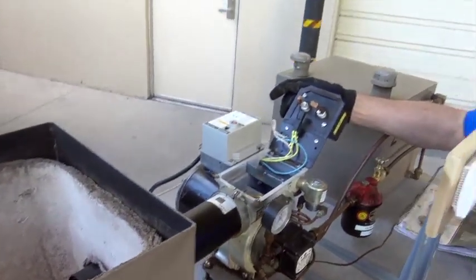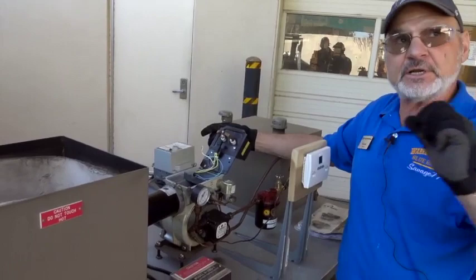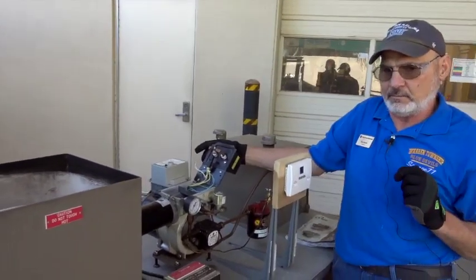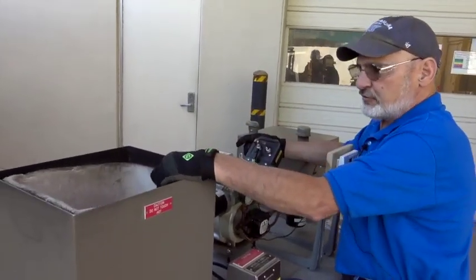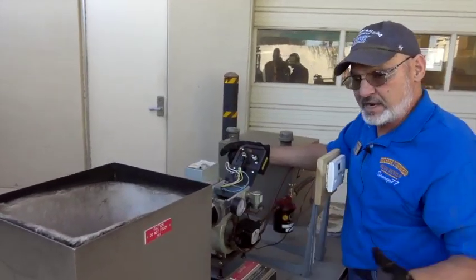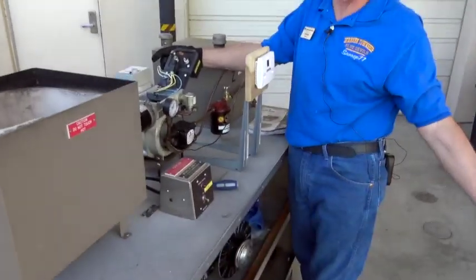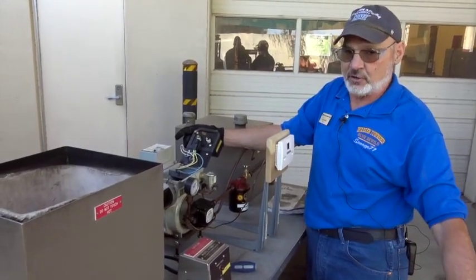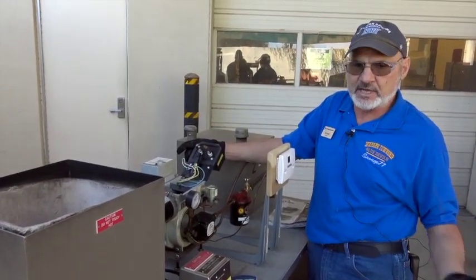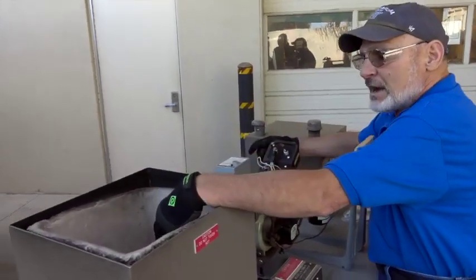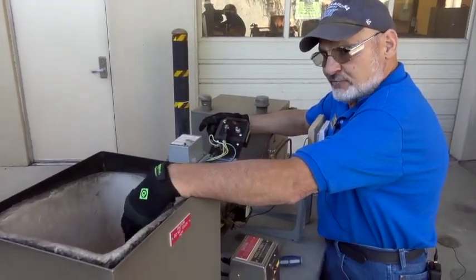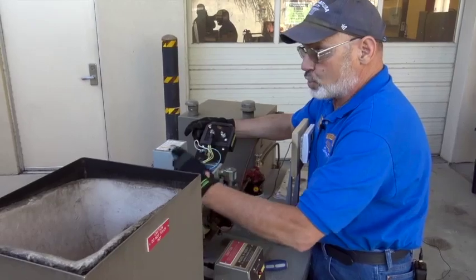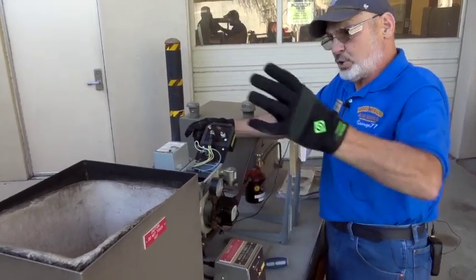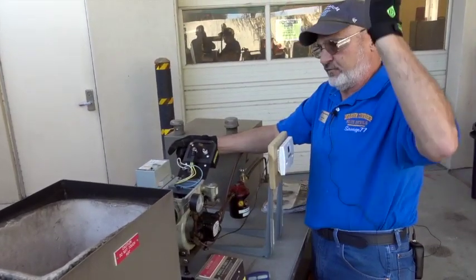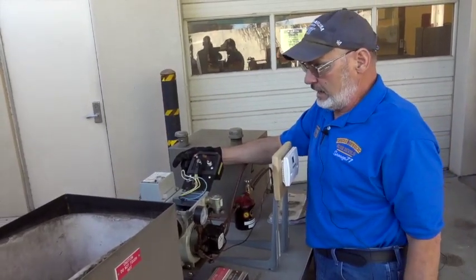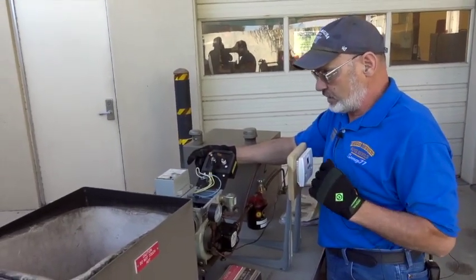Unlike natural gas or propane gas, it's not going to dissipate into the atmosphere. The residual fuel will sit there for a long time. You've been at a gas station where people dump fuel in the gas station. It sits there for a long time. In fact, they got to get absorbent to get this fuel up. If you got a pot full of fuel in here, you're going to have to get all that fuel out after you correct the problem, before you restart that, or you're going to have smoke, you're going to have flame going all over the place, and it could be real fun. Believe me, I've been there before.